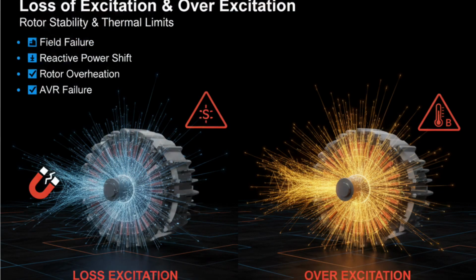Loss of excitation or over-excitation. Loss of excitation occurs when the field current fails. Without proper excitation, the generator cannot maintain magnetic flux and may draw reactive power excessively. Over-excitation results in magnetic saturation, overheating the rotor and stator core. V/Hz protection monitors voltage to frequency ratio to prevent core saturation. AVR malfunction is a common cause of excitation-related problems. This slide visually demonstrates magnetic field lines to help understand excitation behavior.